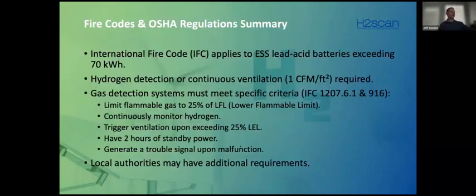Anything that exceeds 70 kilowatt hours, as far as the model codes are concerned, needs to comply with code. That's pretty much an adopted practice with all of the adopted codes, whether it's IFC or NFPA. If you don't have a calculation, then they say that you have to do continuous ventilation. But we're seeing more and more, with the technology today, gas detection systems being integrated with gas purge fans. If you use that type of method as your hazardous mitigation program, then the code states that you have to have a few things present. First of all, you do have to limit the gas to 25% of the lower flammability limit or lower explosion limit. It has to be continuous monitoring.